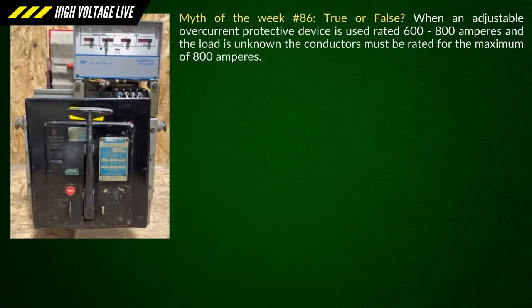And I'll show the only time you do where it tells you to do that, and that's 250.122(B), where you've increased in size, and that could be the voltage drop, correction factors, adjustment factors, or both, or it could be all three of them. But that's the only time you go over and look at Chapter 9, Table 8.